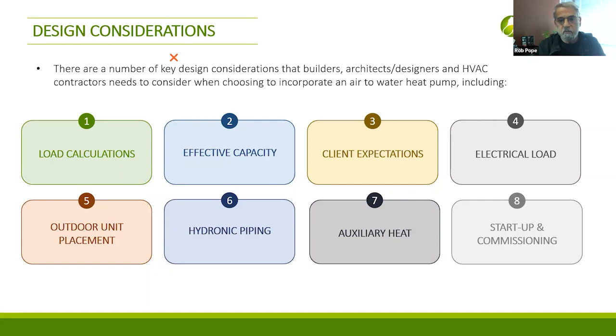And that includes doing proper load calculations. When I say load calculations, I mean the accepted code required methodology for load calculations. If you're not doing that, you're just guessing, and then it's a coincidence if it works. Rule of thumb is not adequate. You need those load calculations to choose the brand and the model within that brand that's most appropriate for the project, that has the right effective capacity, not the nominal capacity.